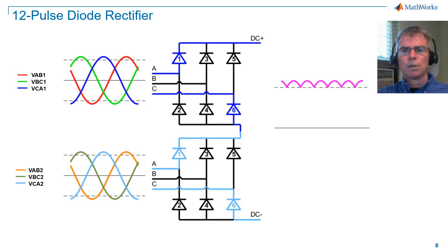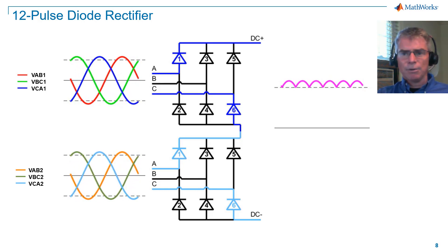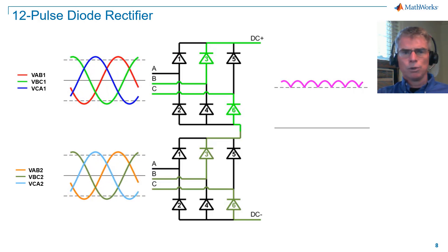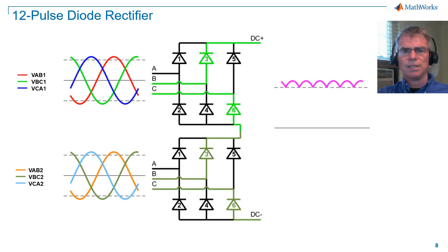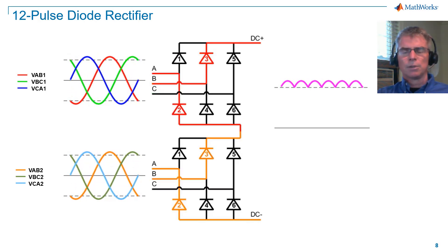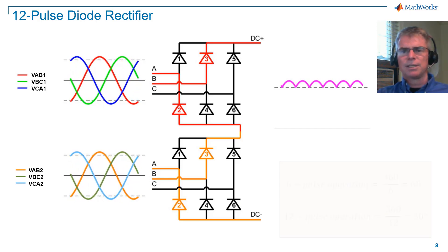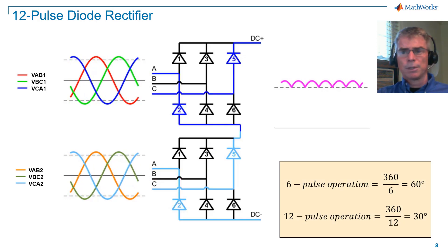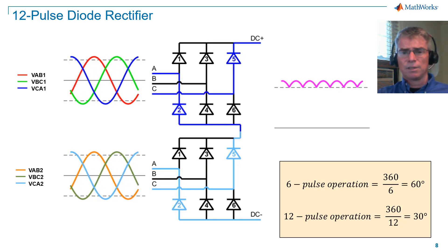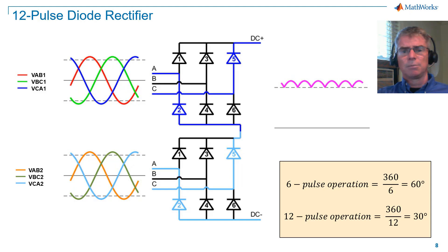If we can have the upper and lower rectifiers switching out of sequence, we should be able to obtain lower ripple on the DC voltage. So six-pulse operation switches at 60 degrees, 360 divided by 6. With a 12-pulse device, we want to switch at 30 degrees, 360 divided by 12.